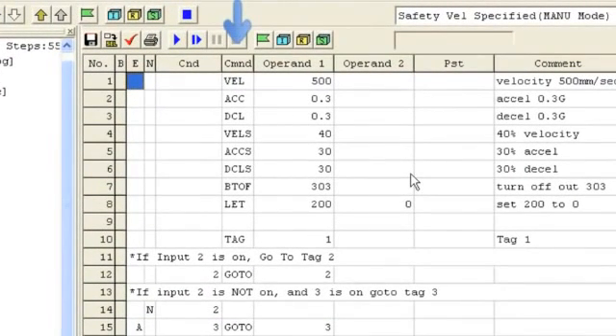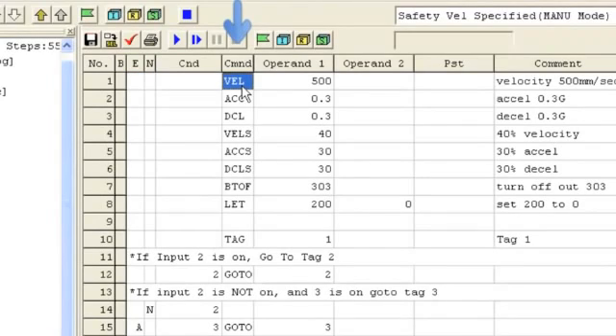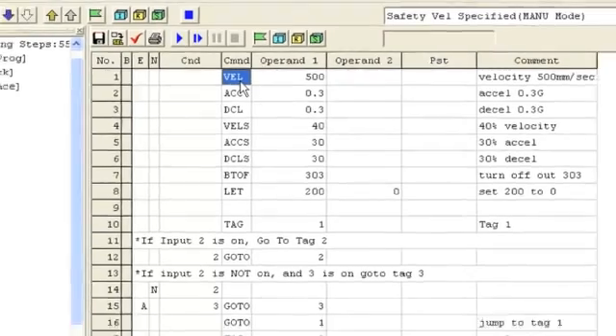The first column we will talk about is the command column. The command column is used to complete a command. A full list of commands with examples is available in the IAI programming manual. The command is mnemonically based, meaning it should closely resemble what the command is trying to do. For example, the home command is HOME. The command to move the actuator is MOVP or MOVL, depending on the move profile. Setting the velocity is VEL, etc.